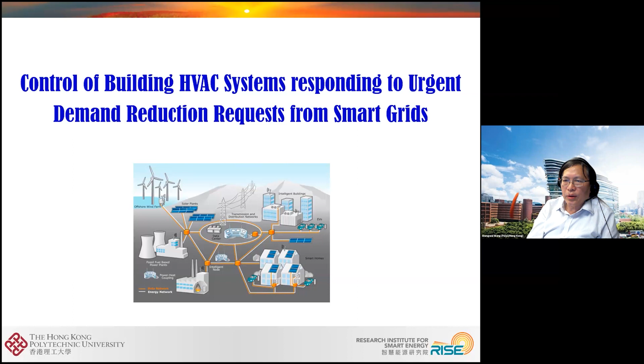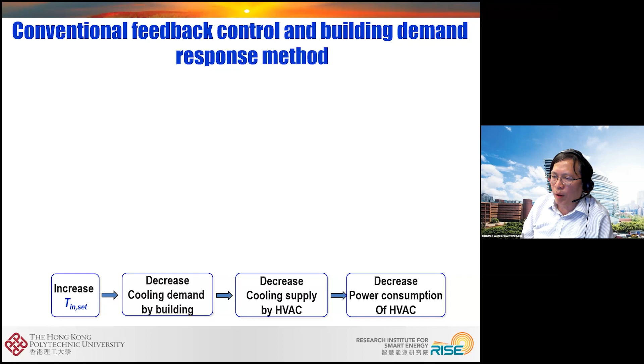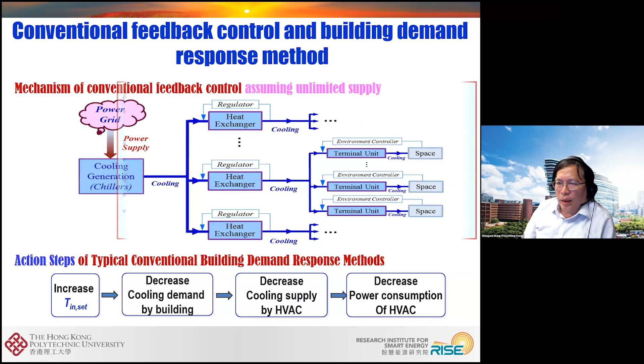For the conventional ways, we can do this rather conveniently. For cooling systems, if it's a heating system we just reverse the control. In the case of cooling systems, if we increase the set point of the space, the cooling demand of buildings can be reduced. Then the cooling supply needed by HVAC systems can be reduced, and eventually we reduce the power consumption of HVAC systems and buildings. This way is rather easy, and conventional control can support this. The advantage is no additional thermal storage is needed, we can have the original cost saving, and conventional control can be used.